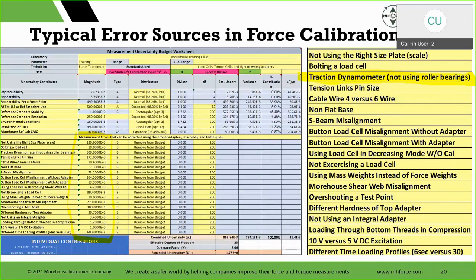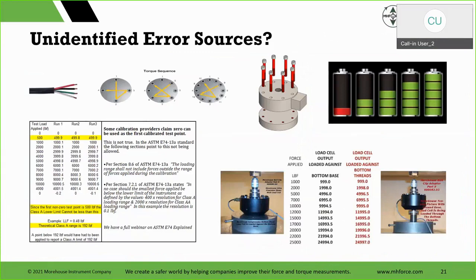Tension links, pin size could be a 0.2% error. Cable, 4-wire versus 6-wire, 0.1%. Non-flat base, you can have 3-4 times the error, 5 times the error, and so on. The different timing profiles, that might be a 0.01. 10 volt versus 5 volt, typically that error is less than 0.01. But they all add up, right?